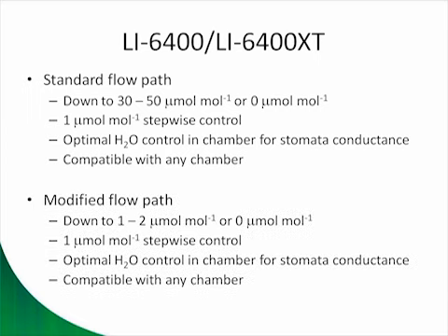In the LI-6400, chamber CO2 concentrations can be controlled down to 30 to 50 micromoles per mole depending on machine. This makes it harder to assess the CO2 compensation point in C4 plants. By modifying your system, we are able to achieve a concentration of 1 to 2 micromoles per mole CO2 while still maintaining optimal conditions for gas exchange.